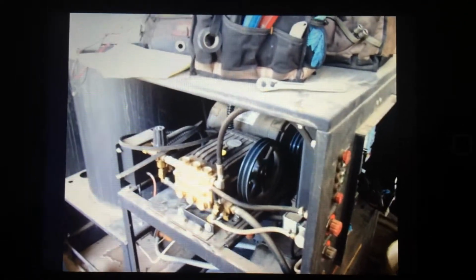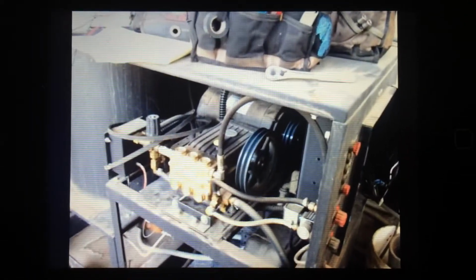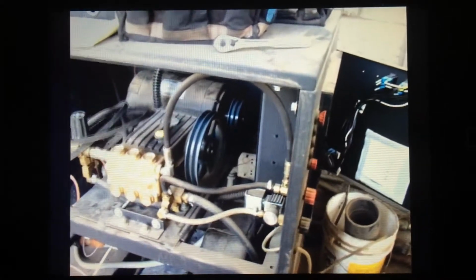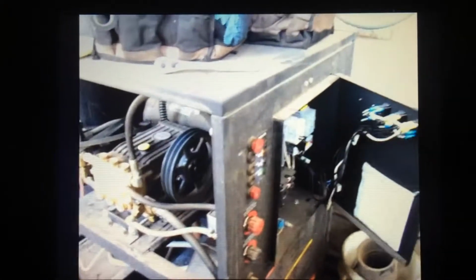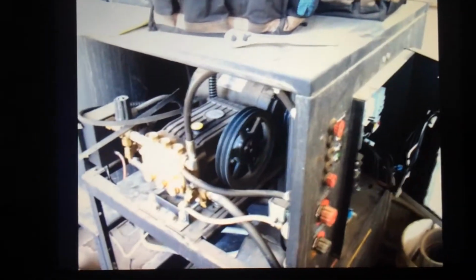We're going to talk about troubleshooting whether or not there's a bad electric motor. This happens to be an IDM machine. It doesn't matter really what machine it is. If it's got an electric motor, the procedures are the same. Customer complaint here was that the motor is making a growling sound and kicking the breaker. We wanted to verify whether or not it truly is a bad motor.